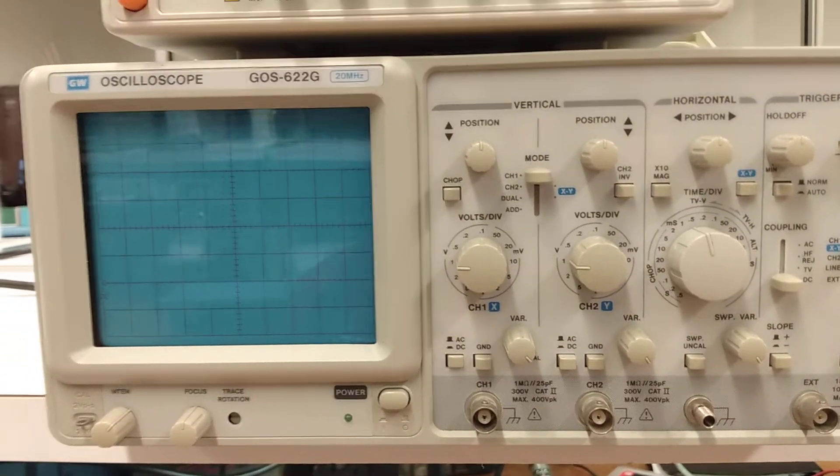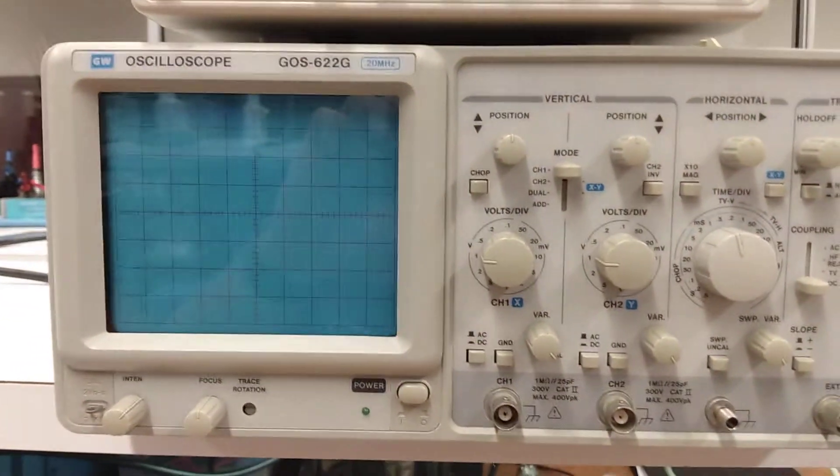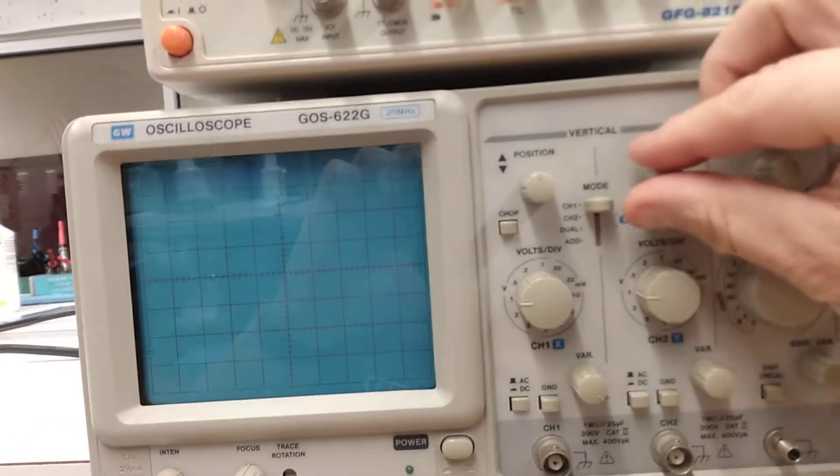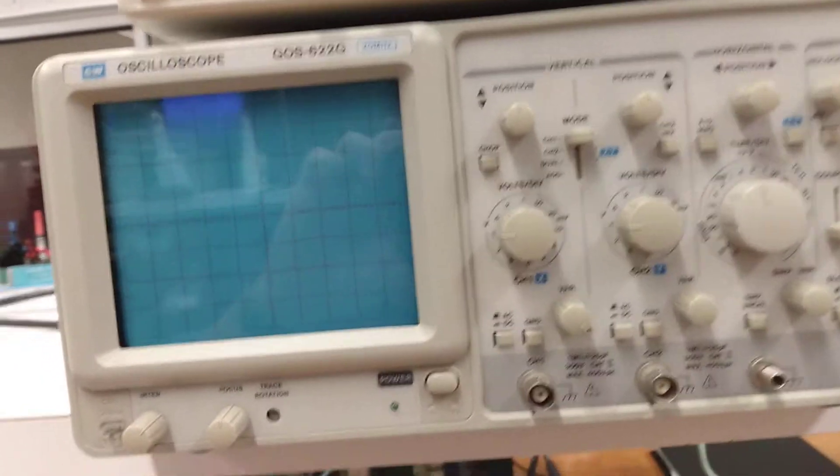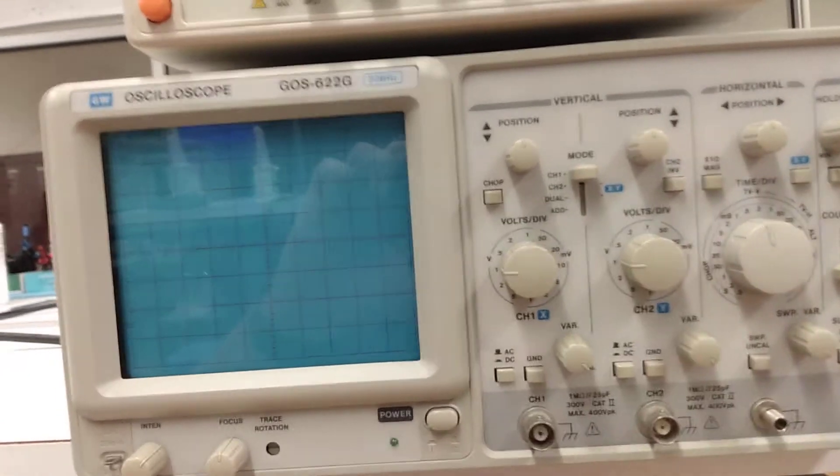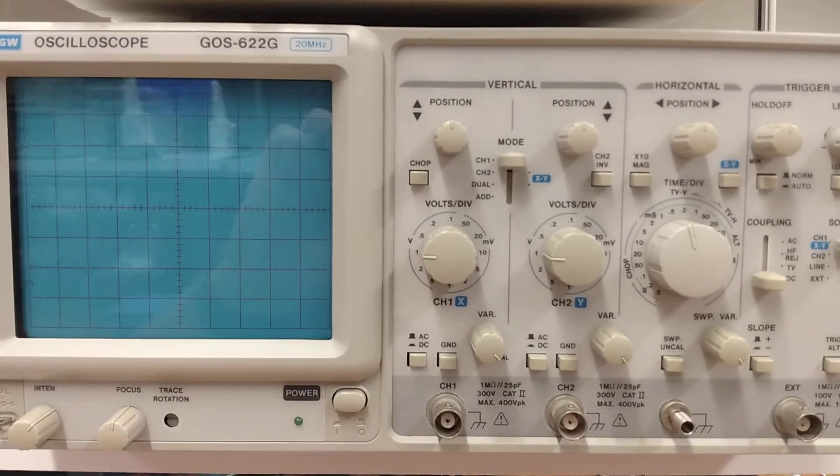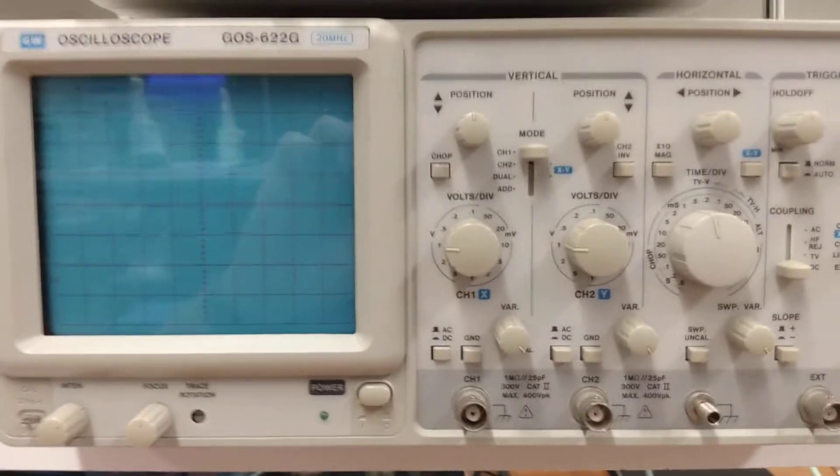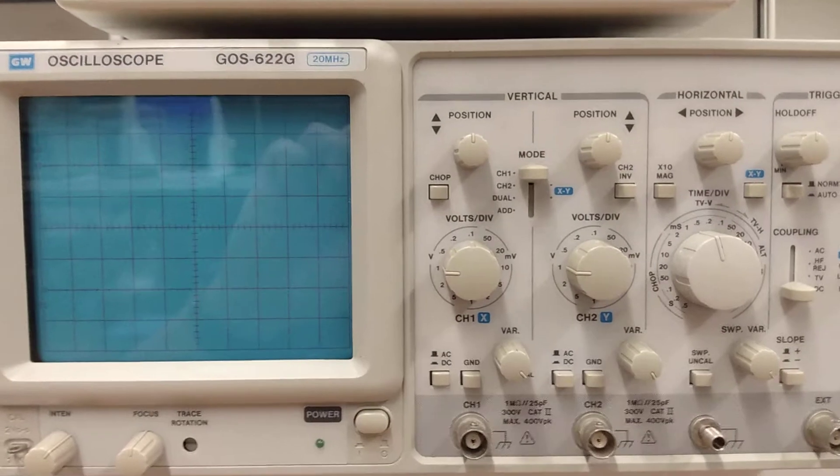Before you begin, a basic way to get started when using the oscilloscope is turn all of our knobs on the top here to the 12 o'clock position. Turn your volts per division to one volt per division initially. We'll start out with a 0.5 millisecond setting on our time. You want to make sure your trigger pickup is in the auto mode to begin with.